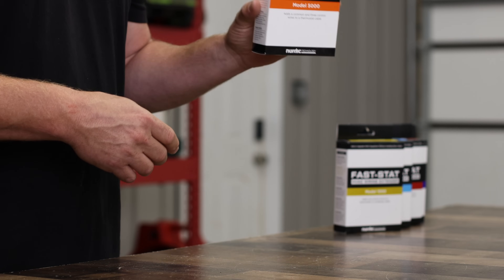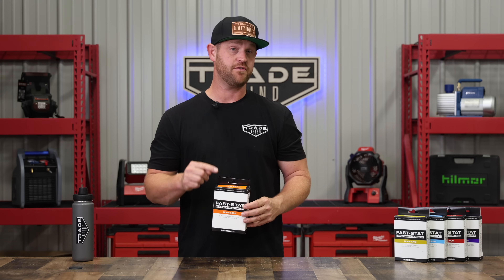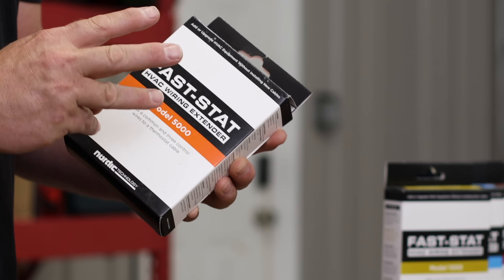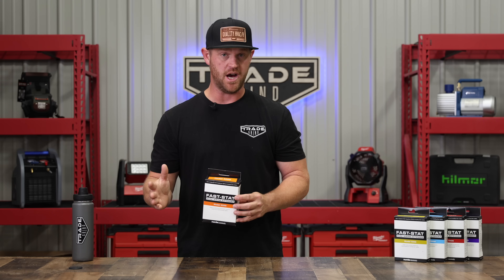So I got to thinking, what can I do to facilitate this project the way the customer wants it? So I picked up the Fast-Stat model 5000. This particular model is exactly what I needed — it actually adds a common wire and then three control wires, so it had more than enough for this particular job.